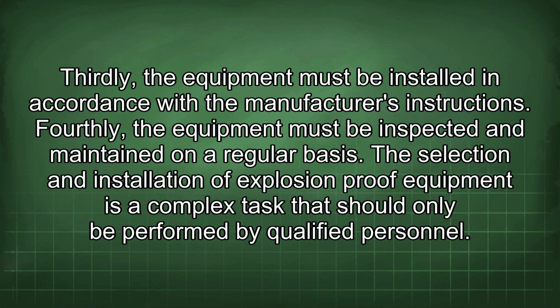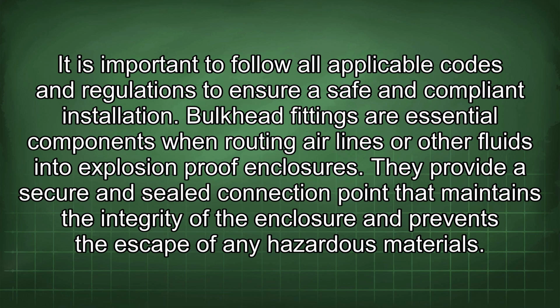Thirdly, the equipment must be installed in accordance with the manufacturer's instructions. Fourthly, the equipment must be inspected and maintained on a regular basis. The selection and installation of explosion-proof equipment is a complex task that should only be performed by qualified personnel. It is important to follow all applicable codes and regulations to ensure a safe and compliant installation. Bulkhead fittings are essential components when routing air lines or other fluids into explosion-proof enclosures. They provide a secure and sealed connection point that maintains the integrity of the enclosure and prevents the escape of any hazardous materials.